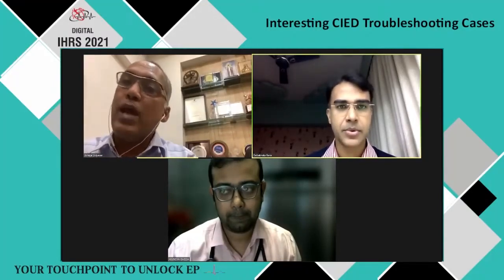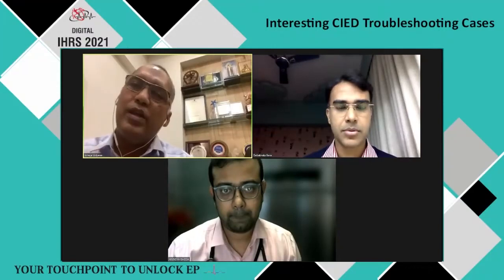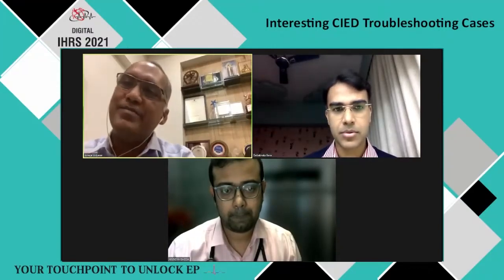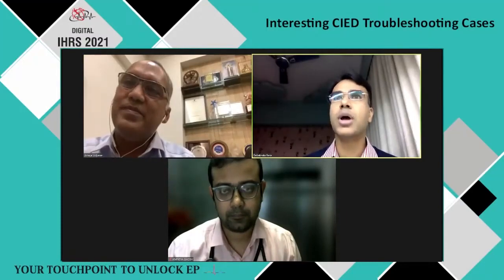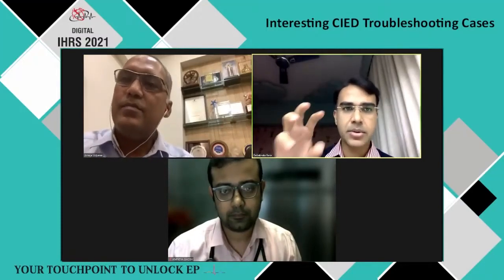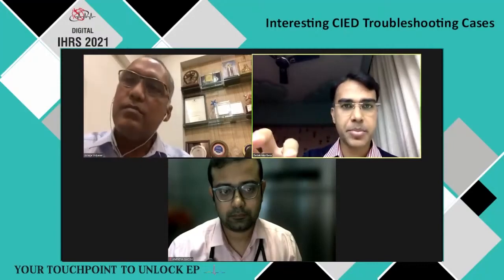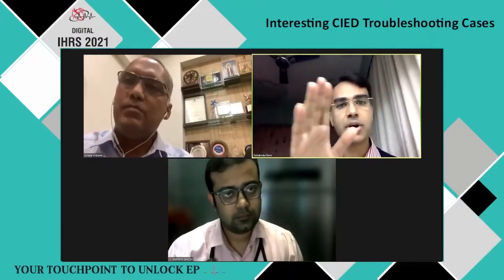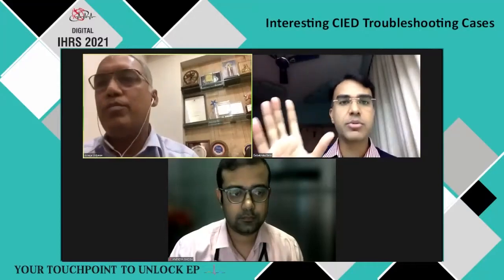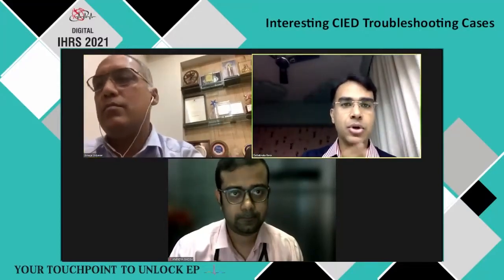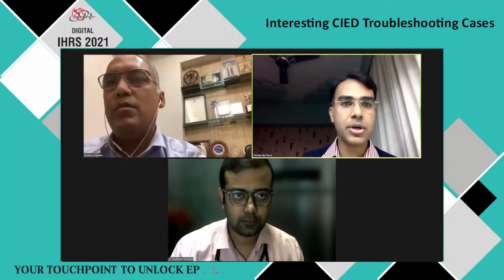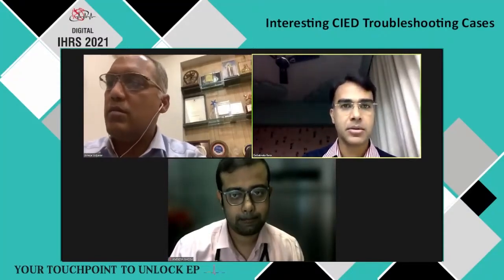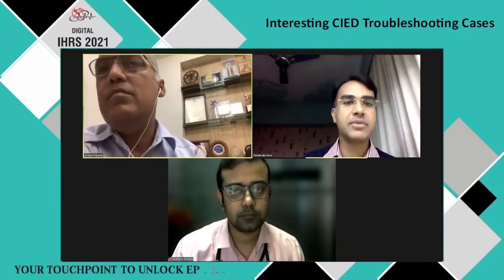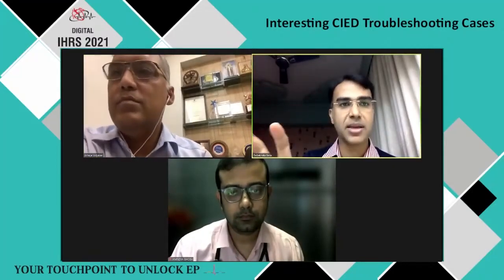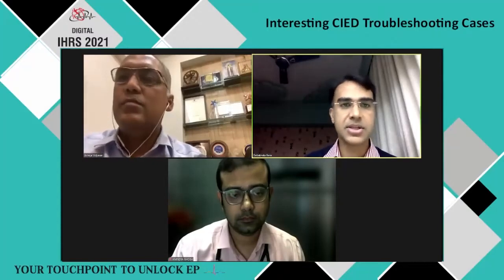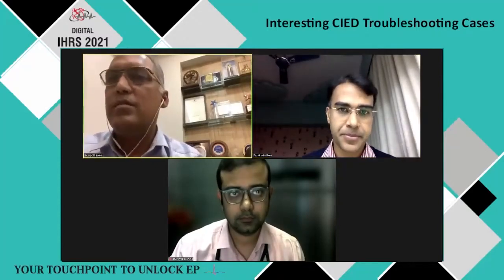Right. And what would happen to your capture algorithm or evoked potential algorithm if you keep a magnet? So if you put a magnet on a pacemaker, the auto capture algorithm for that time will be stopped, paused rather. And what it will do is pace 1 volt higher than the last measured auto capture threshold. So if 1.5 was the last measured threshold, for the time being it will pace at 2.5, at the set pulse amplitude. Correct. Right, very nice.